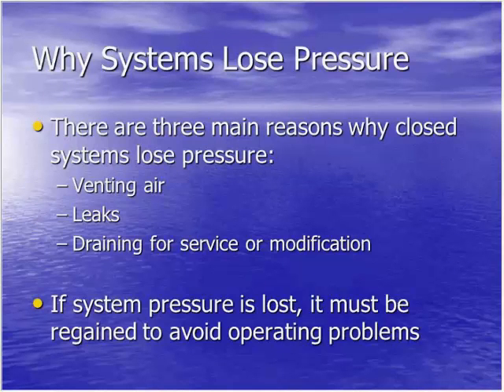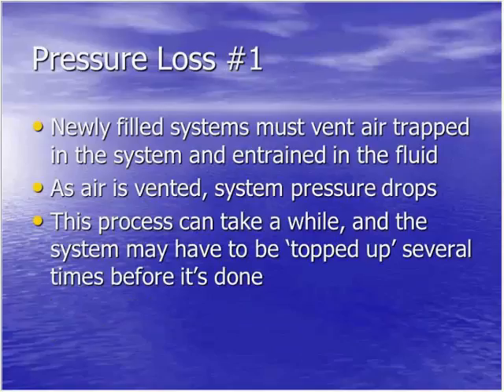So, venting of air. Newly filled systems must vent air that's trapped in the system and entrained in the fluid. Typically, if you fill a hydronic system and you properly purge all the big air bubbles out of it, 3 to 5% of that total system volume is going to be air that is entrained in the fluid. Much like that glass of water you get before you go to bed, you wake up in the morning, there's all these bubbles on the side of the glass that came out of the fluid, that were entrained in the fluid.